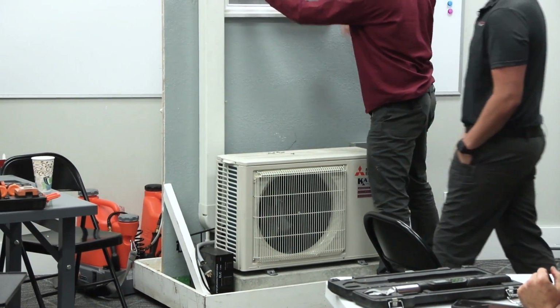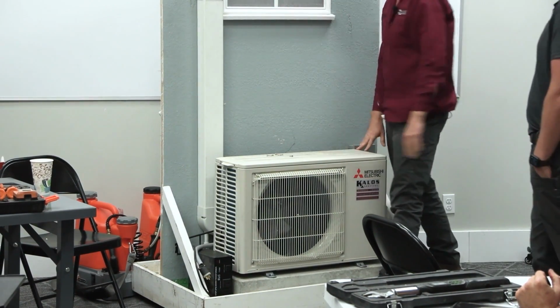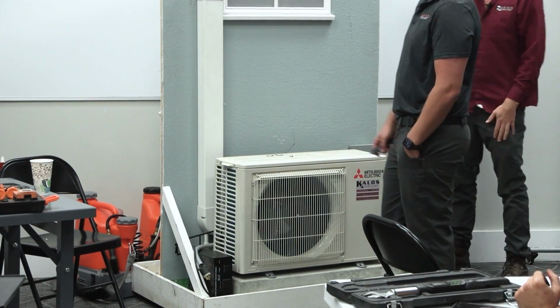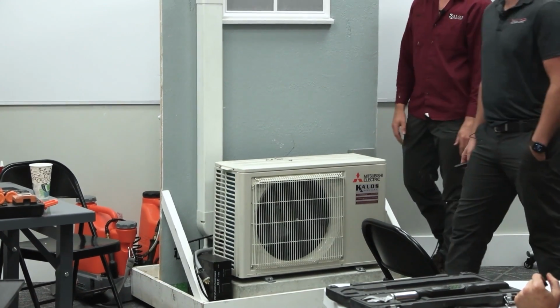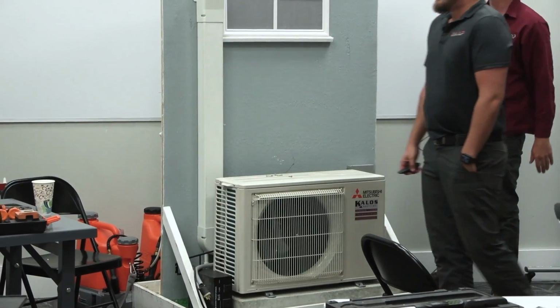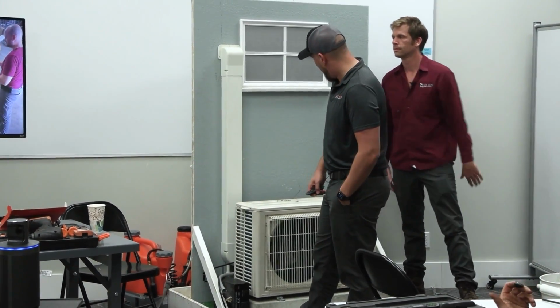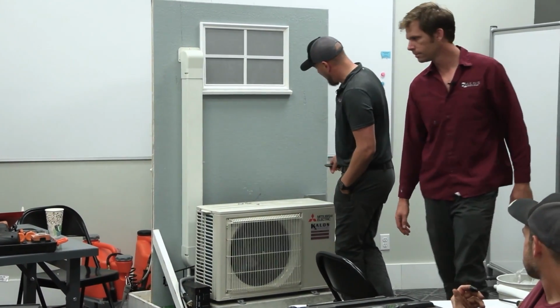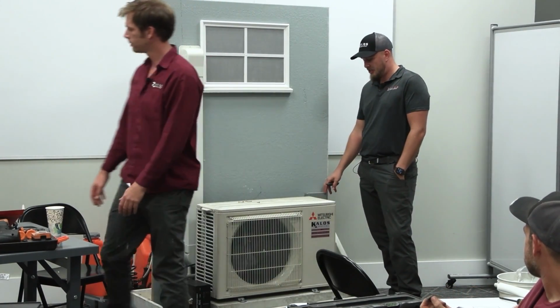So on the outdoor unit, we have our fan motor, outdoor coil, compressor, and our EXV—electronic expansion valve. Moving down the line, we have our high voltage. Unlike a regular changeout, a lot of these units are ground-up installations, so we have to run power from the breaker panel through the attic down to our condensing unit, and then from the condensing unit to our indoor unit.